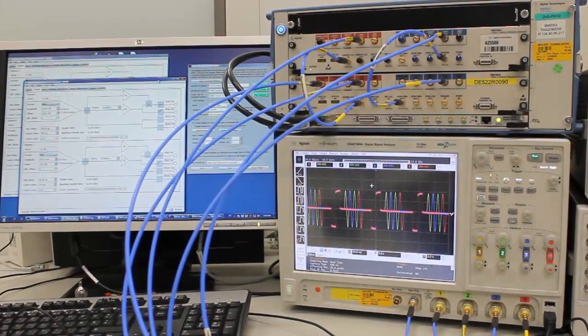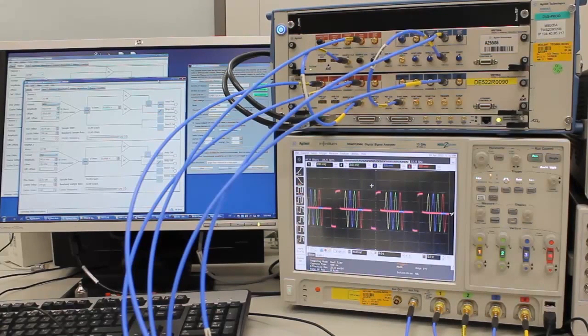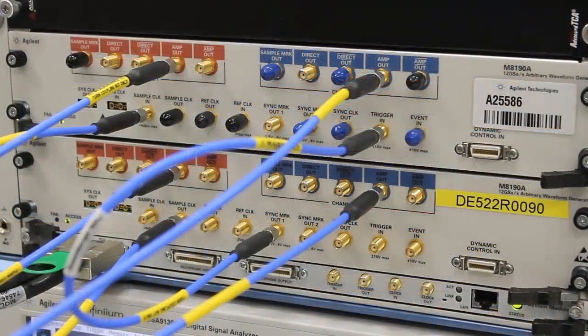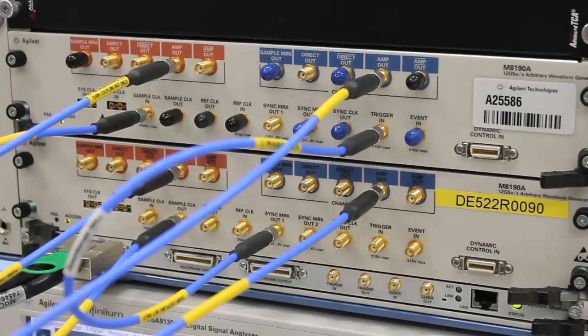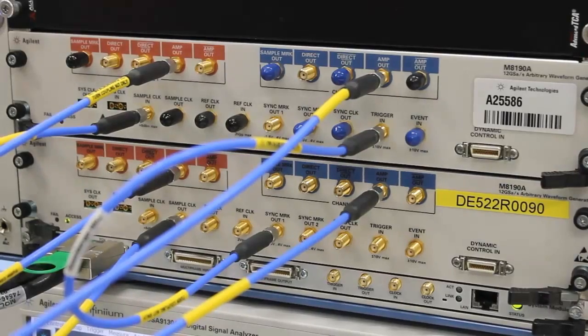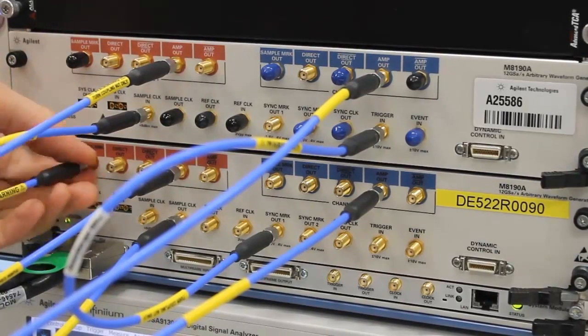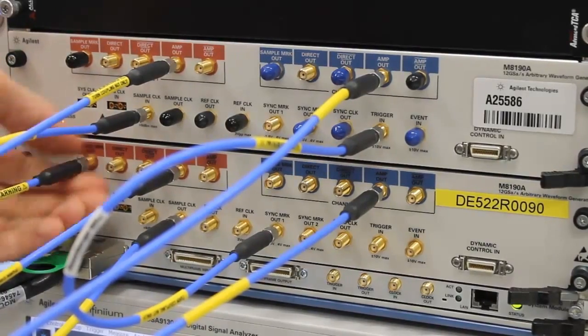Let's take a look at this setup. For the purpose of this demonstration, we are using two M8190 modules with their outputs connected to an oscilloscope. In a real setup, one could use the marker outputs for de-skewing so that the analog AWG outputs can remain connected to the device under test.